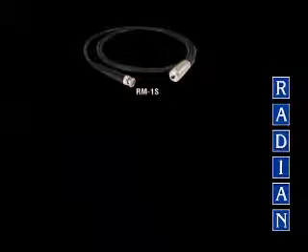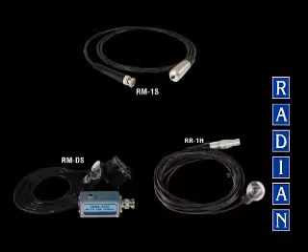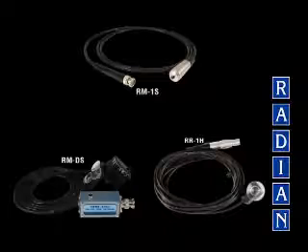A meter test can be executed by using a snap switch, the Enter button on the keypad, or the many sensors offered by Radian Research that will sense disk revolutions, infrared, and visible calibration pulses, as well as KYZ signals. In this video, we will demonstrate a pulse pickup sensor-based test.